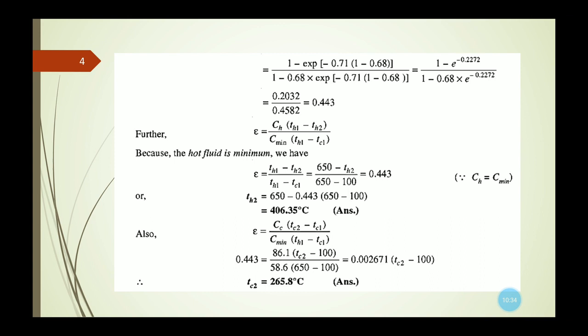Again, the effectiveness is represented as Cc multiplied by Tc2 minus Tc1, divided by C min multiplied by Th1 minus Tc1. So if we put all the values which are known to us, we can calculate the outlet temperature of the cold fluid, we are getting 265.8 degrees centigrade.